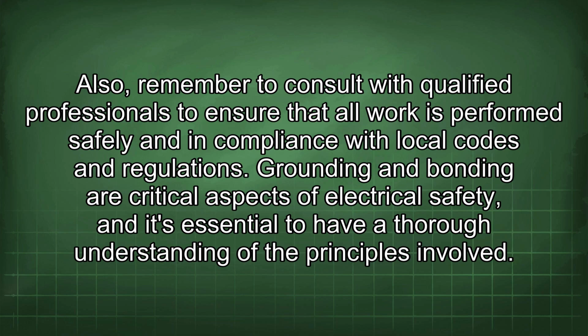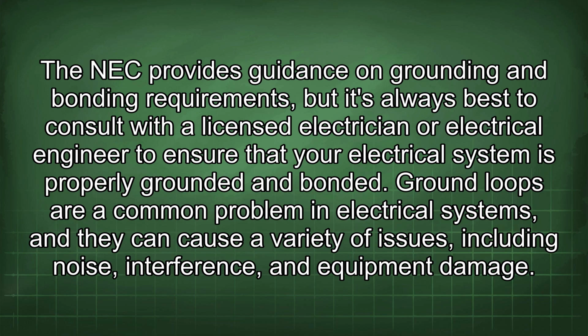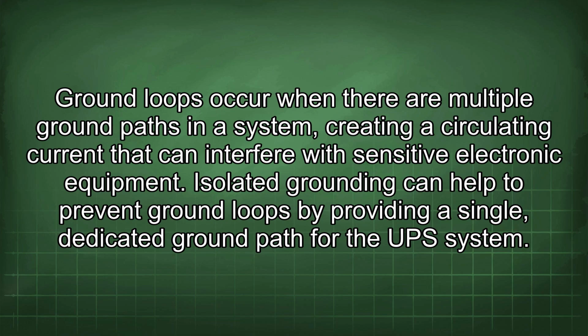Grounding and bonding are critical aspects of electrical safety, and it's essential to have a thorough understanding of the principles involved. The NEC provides guidance on grounding and bonding requirements, but it's always best to consult with a licensed electrician or electrical engineer to ensure that your electrical system is properly grounded and bonded. Ground loops are a common problem in electrical systems, and they can cause a variety of issues, including noise, interference, and equipment damage. Ground loops occur when there are multiple ground paths in a system, creating a circulating current that can interfere with sensitive electronic equipment. Isolated grounding can help to prevent ground loops by providing a single, dedicated ground path for the UPS system.